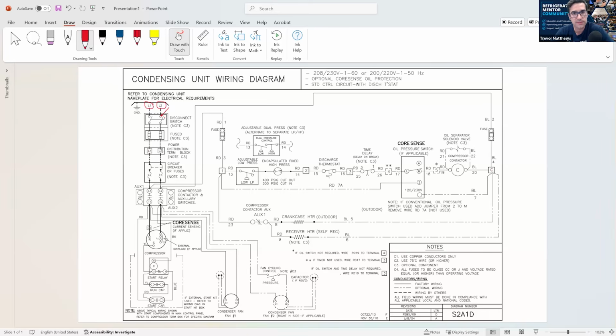You want to do this on a system that works. I want you to go in there and test it. You can sit and listen to this, you can sit and watch it, until you go out there and test it safely. So what do you mean, how do I test it? The first thing you want to check is, is there power coming into the main? So you can take your one lead, and if it's plugged in there, you go to ground and say, oh, I got 115 volts, or 120, whatever it is. So now we know there's power coming into L2.